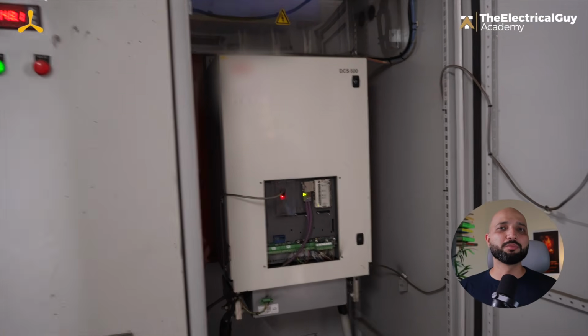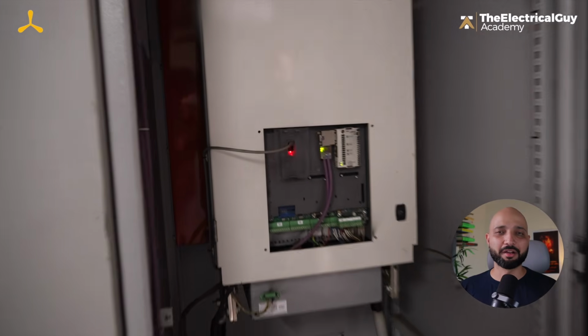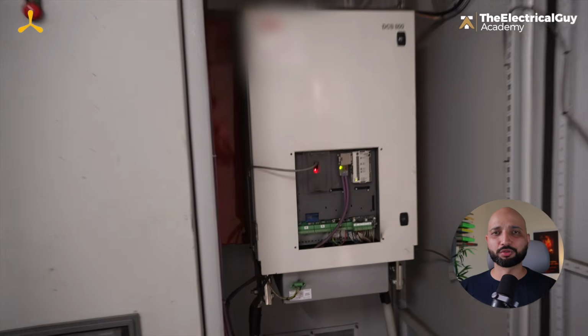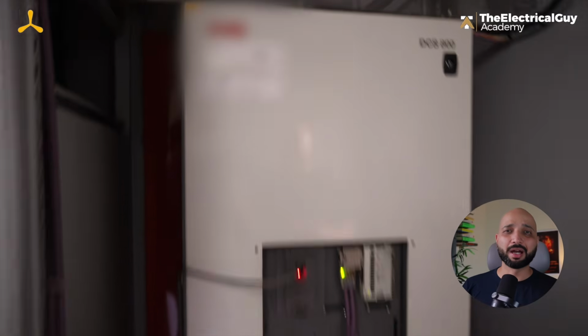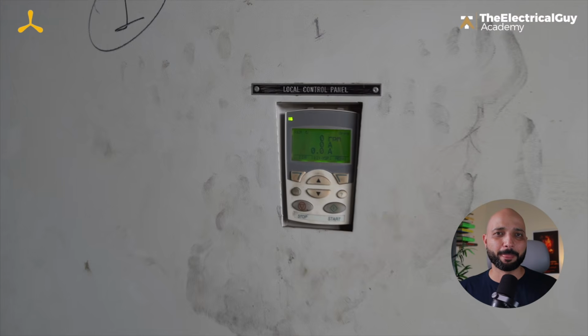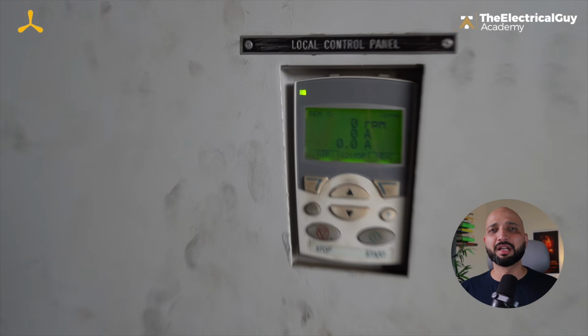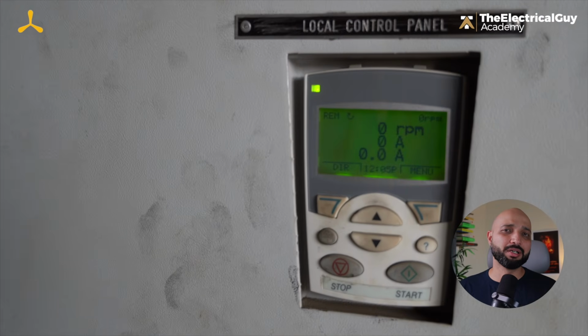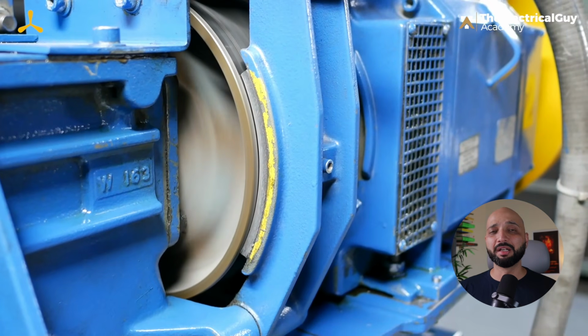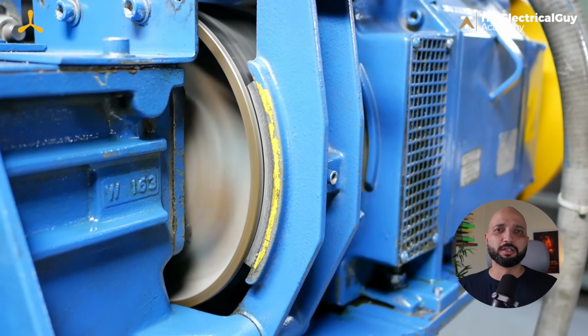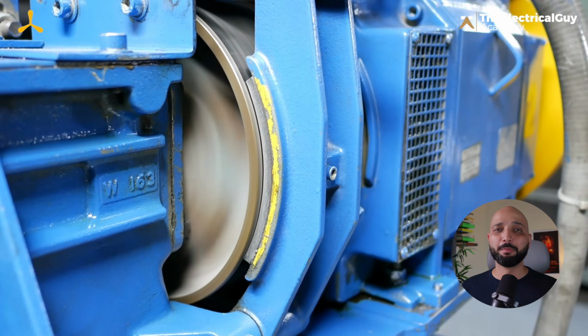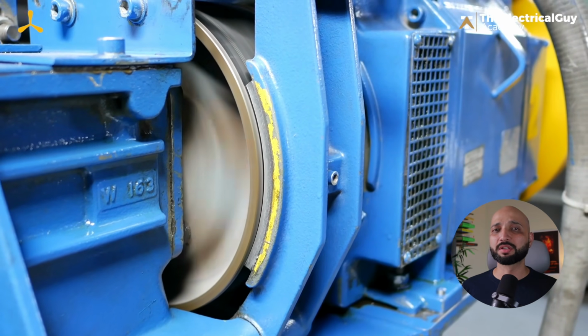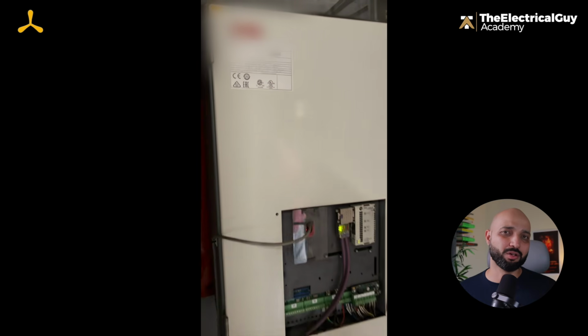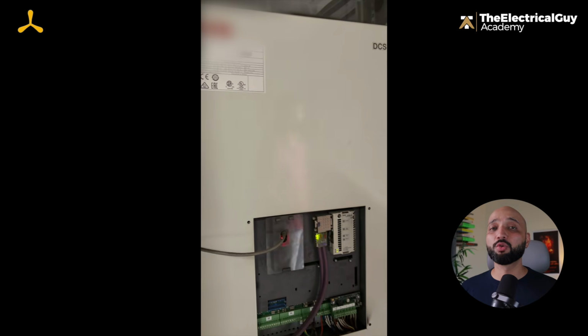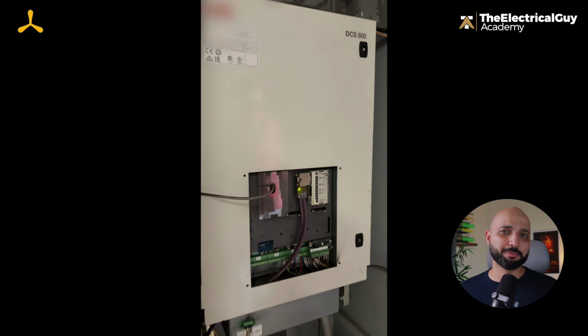The speed of the DC motor is controlled using a DC drive. A modern DC drive is a microprocessor controlled system that precisely regulates the speed, torque and power of the motor. It does this by converting incoming AC power into adjustable DC power using a thyristor or SCR bridge. The speed of the DC motor can be controlled mainly in two ways, by armature voltage control and by field flux control. This gives the DC motor a very wide and flexible speed control range.